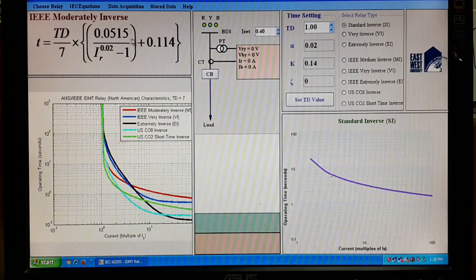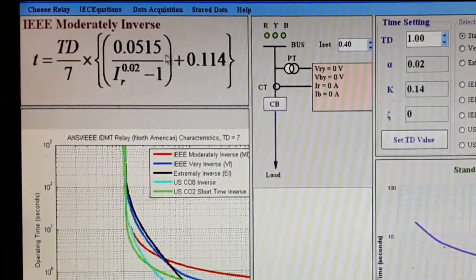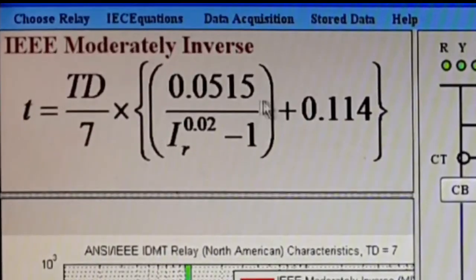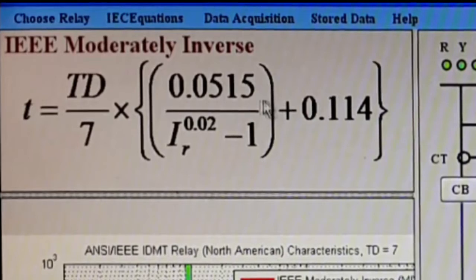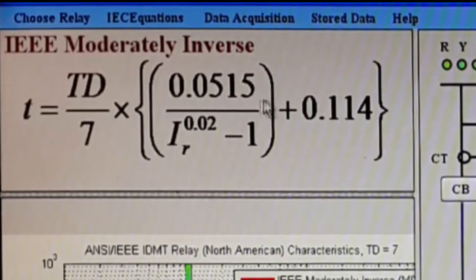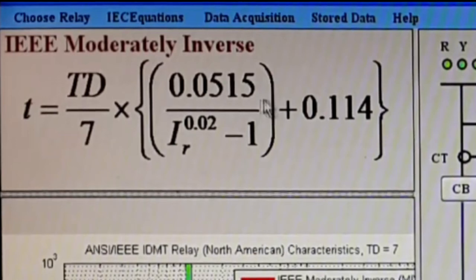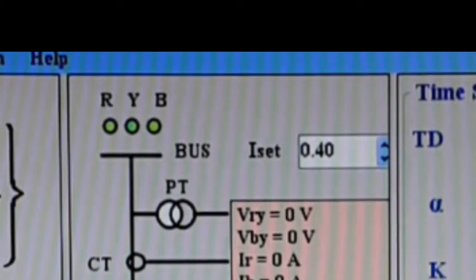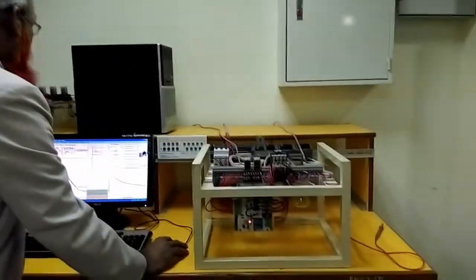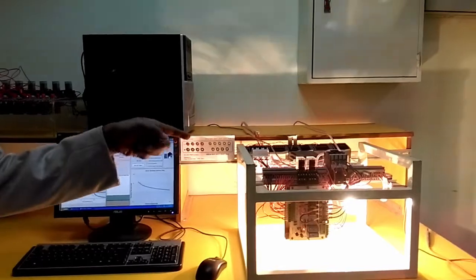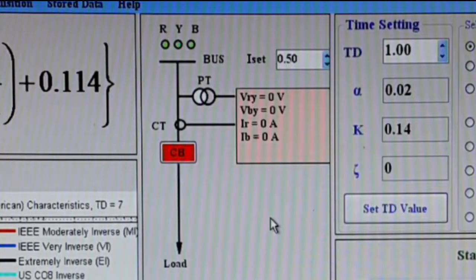Let us start the relay. In our over-current relay, we use IR, which is the ratio of the actual current to the set current — I divided by I-set equals IR. The I-set value can be entered here; we are putting it as 0.5. Now it is starting. You can start or close the breaker by clicking this push button, and you can see the color is red now.